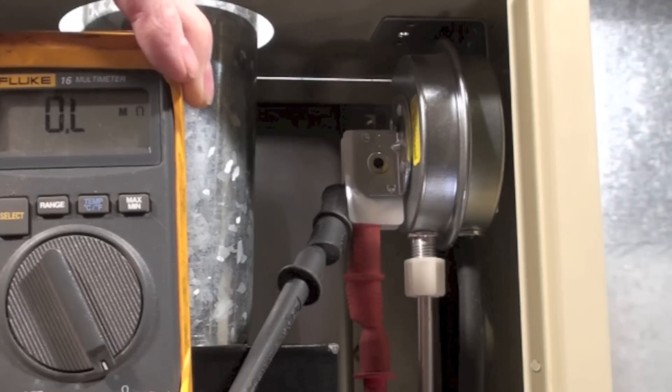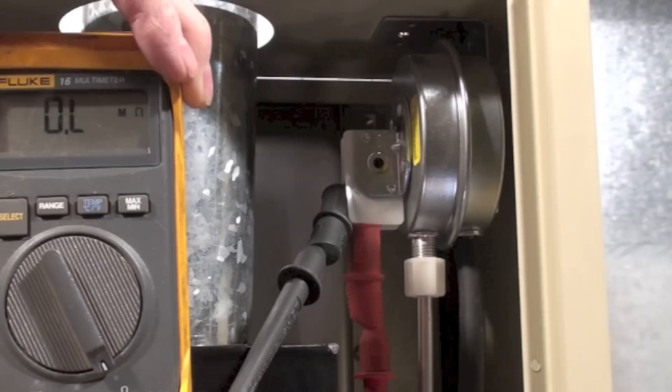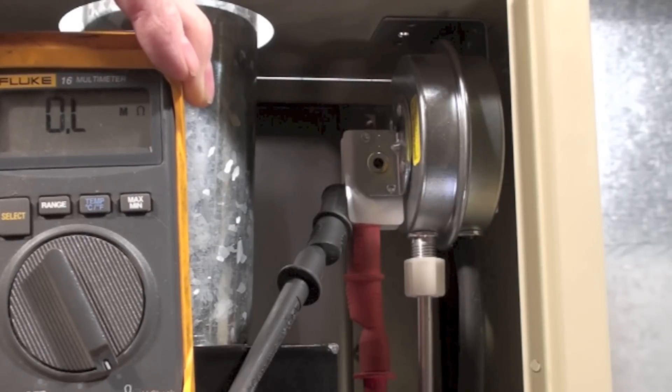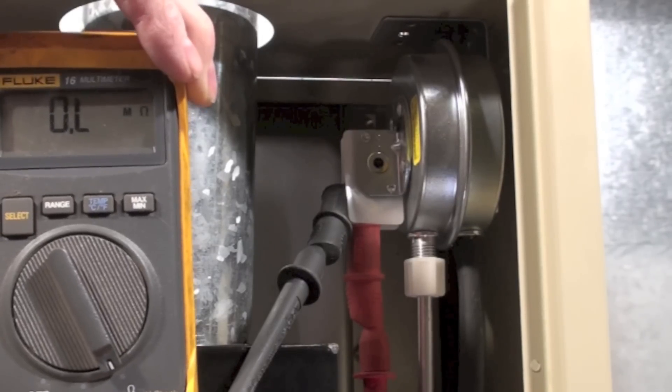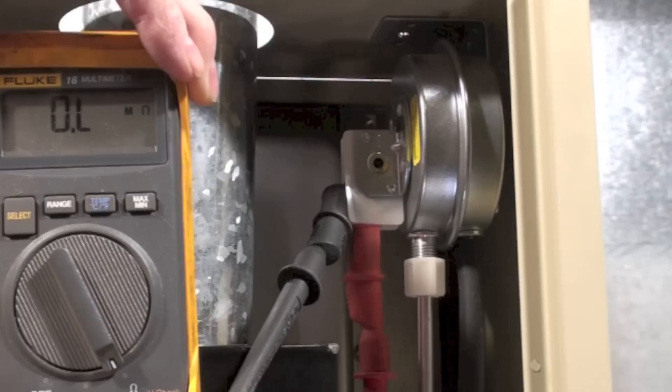In this case it was just a pressure switch problem. It doesn't mean the pressure switch is bad - it may very well mean you got a blocked vent or blocked combustion.